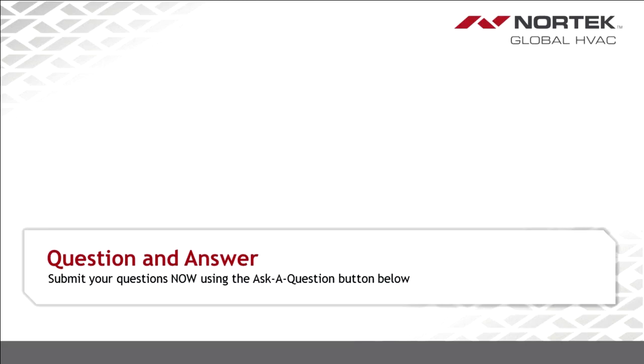Okay, Greg. Well, we really are just about out of time. Only got maybe a minute of time left here. We do have one more question, and that question is concerning dual fuel systems. Is there any type of recommendation as far as the deadband on the thermostat between the heat pump coming in versus the gas furnace, or do we have any kind of a recommendation in terms of degrees, whether it be 2 to 5 or whatever the case may be? So you're talking differential between first and second stage.